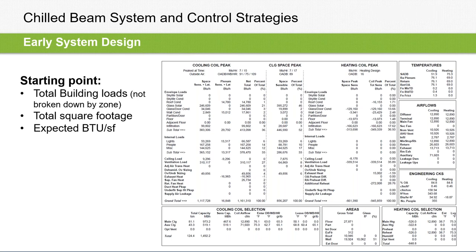But that's a good way to start a discussion. Then also the latent load, you can typically base that off of the occupancy, a couple hundred BTUs of latent energy per person. So if you know what you expect the building occupancy to be, you can get an idea of what your latent load would be as well. So that's a good way to get your baseline or early discussion sensible loads and latent loads.